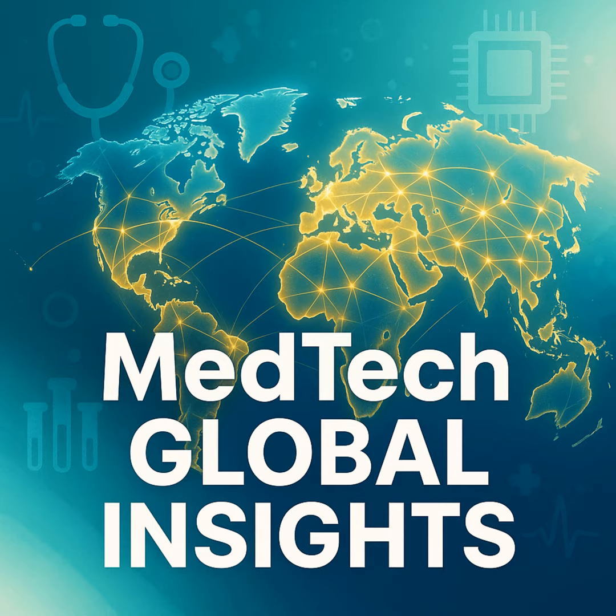Compounding this, the new EU AI Act runs in parallel to the MDR. This means most AI medical devices are also deemed high risk under the AI Act, creating a dual compliance burden where your technical documentation must satisfy two different overlapping sets of regulations.